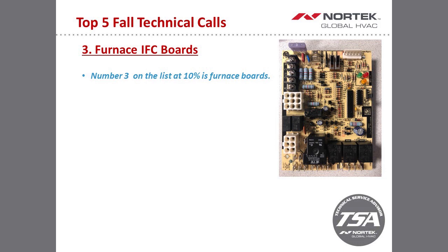This is probably, along with the limit and pressure switch circuit, guys will just replace parts and try not to track down either a voltage drop potentially to your gas valve, and they automatically think it's a board. Most of the time, it's not a board issue in regards to a troubleshooting call. That's probably the last thing I would tell a guy to replace is the actual circuit board, because we're going to be going through the limits and pressure switch circuit depending on what the call is into tech.